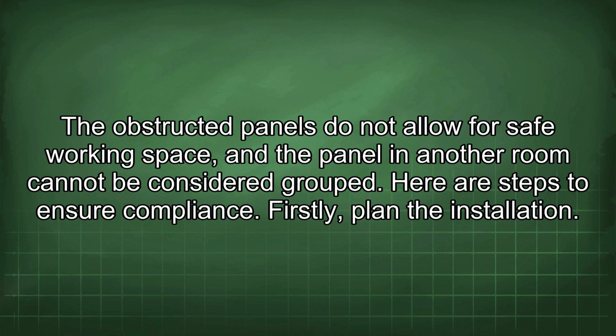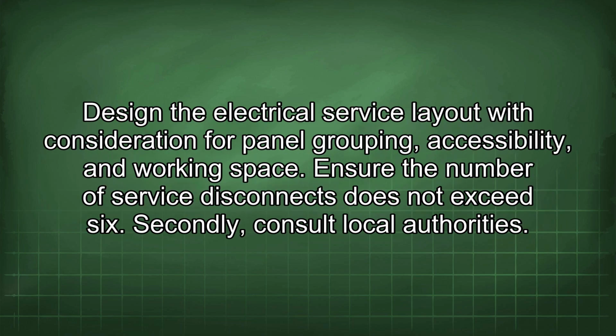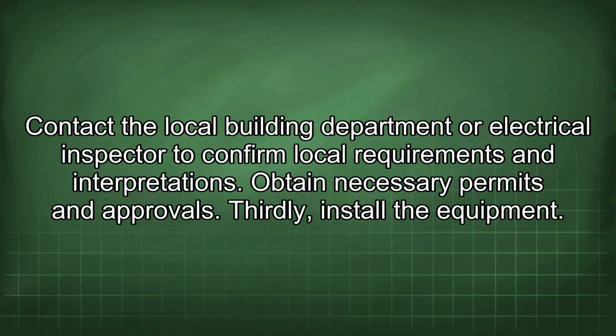Here are steps to ensure compliance. Firstly, plan the installation. Design the electrical service layout with consideration for panel grouping, accessibility, and working space. Ensure the number of service disconnects does not exceed 6. Secondly, consult local authorities. Contact the local building department or electrical inspector to confirm local requirements and interpretations. Obtain necessary permits and approvals.